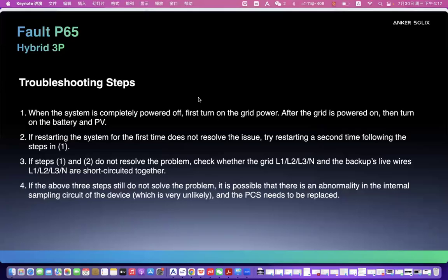Next, having finished the meter and the DC cable part, this is P65. What does this mean? It's some PCS connection loosened. If this issue happens, you just switch off the machine, wait around 2 minutes and restart it. It will be fine. It's easy to solve this problem, and it does not happen frequently. Just make sure this solution works.